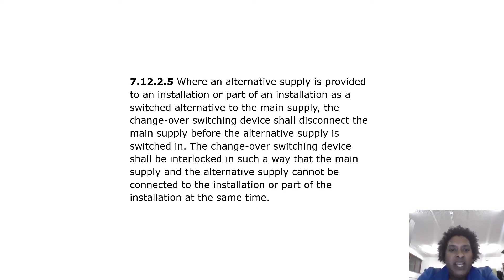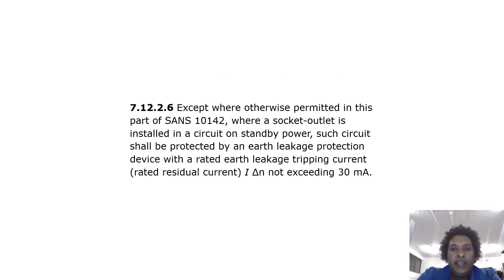Where an alternative supply is provided as a switched alternative to the main supply, the changeover switching device shall disconnect the main supply before the alternative supply is switched in. The changeover switching device shall be interlocked so that the main supply and the alternative supply cannot be connected at the same time. Where a socket outlet is installed in a standby power circuit, such circuits shall be protected by an earth leakage protection device with a rated earth leakage tripping current not exceeding 30 milliamps.